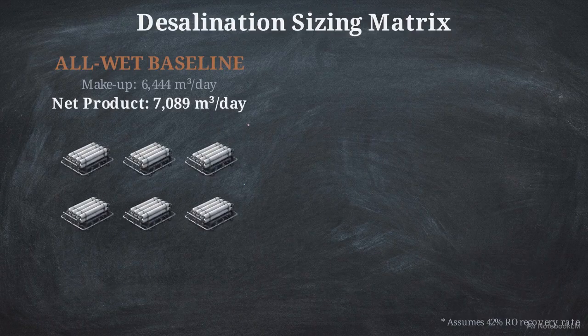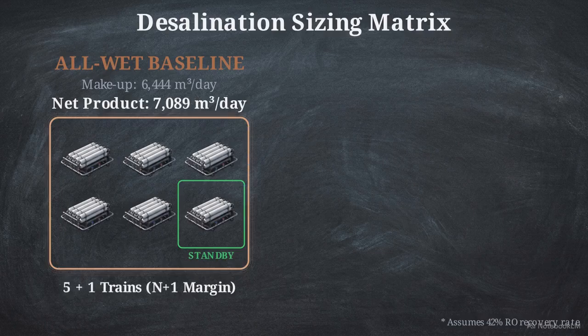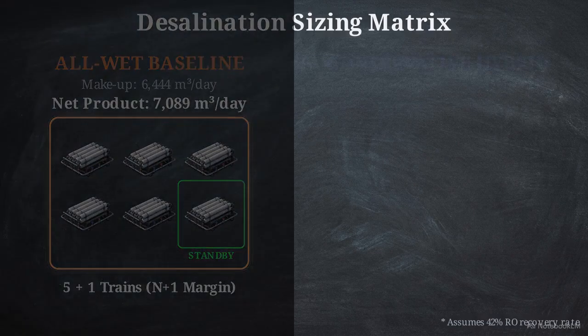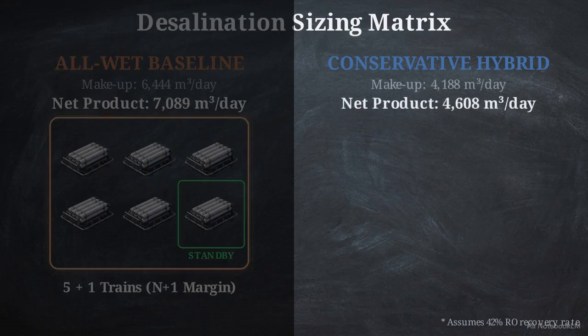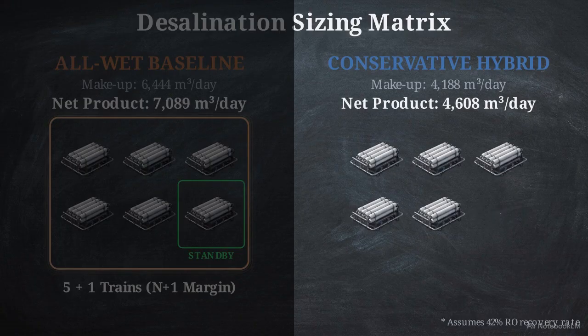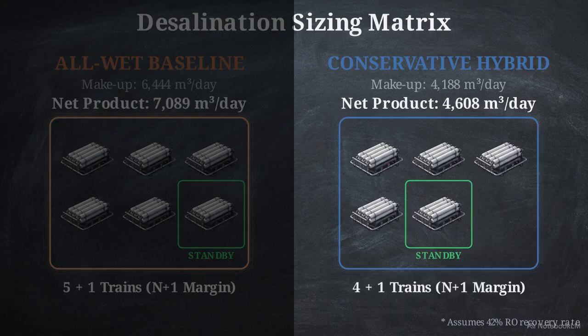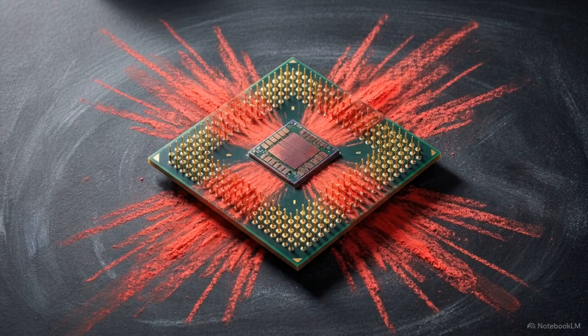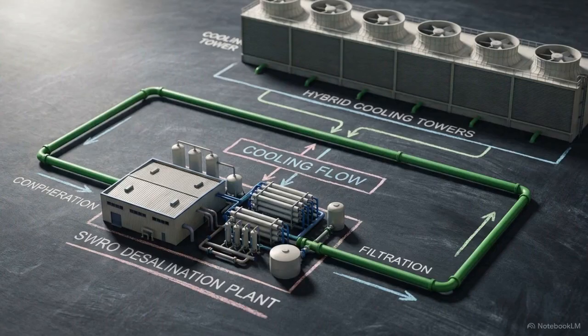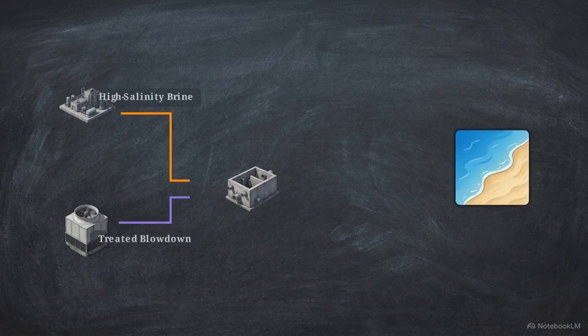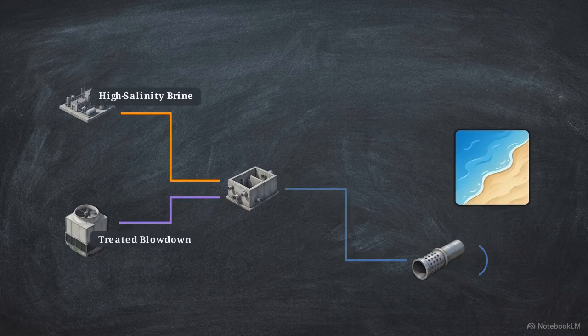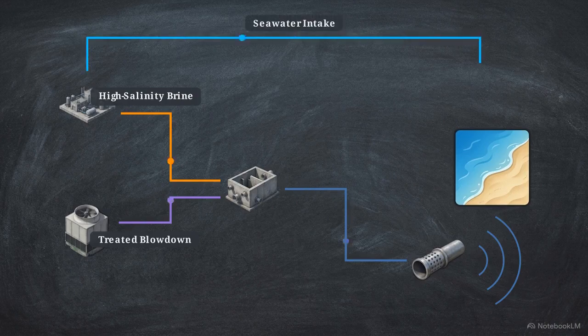Servicing the all-wet baseline requires 6 installed RO trains to meet the daily volume while maintaining an N+1 margin. If the facility operates on a conservative hybrid architecture, the net product requirement drops, allowing the plant to shrink to 5 installed trains. While the 144 megawatt IT load defines the magnitude of the thermal rejection, it is the cooling tower strategy that determines the variable scale and final train count of the SWRO plant. Reject streams from the process, including high salinity brine and treated blowdown, require strict neutralization and tidal modeling to ensure they do not recirculate into the marine intake.